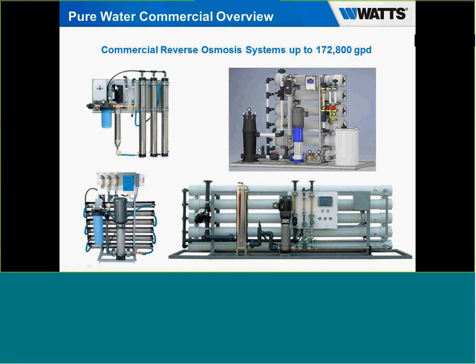If you require higher volume than the wall mount, we get into our floor mount. These start out at 3,600 gallons per day, and this particular model goes up to 10,000 if you have the six membranes. That's how we achieve the different RO productions, by the number of membranes. And so this system here goes from 3,600 gallons per day up to 10,800 gallons per day.